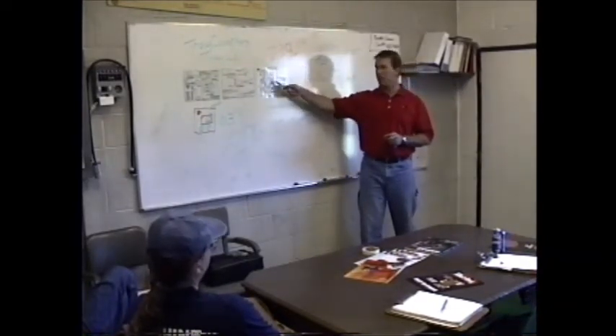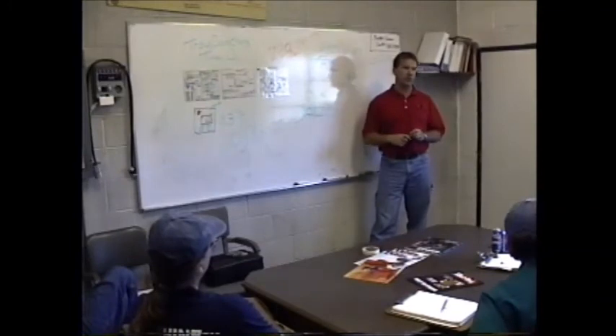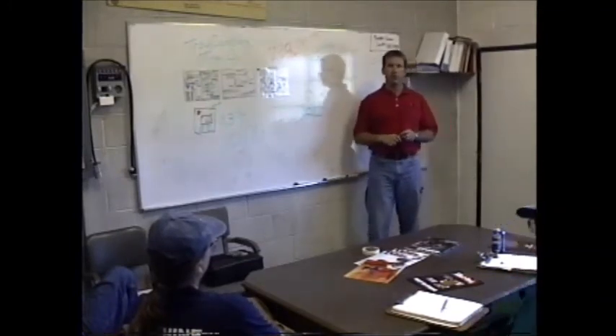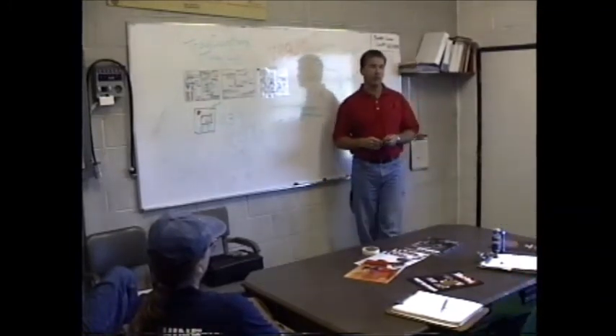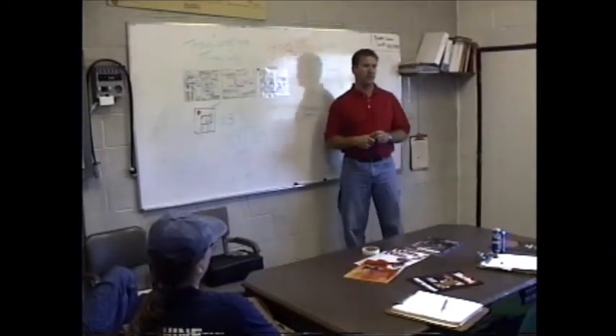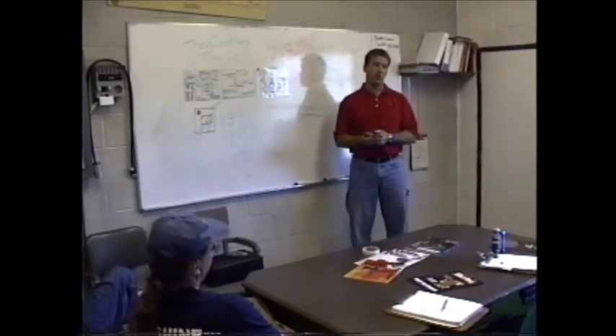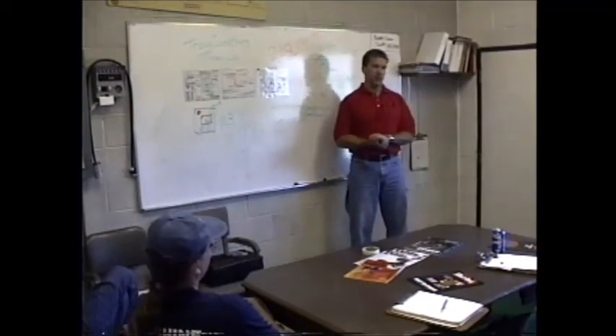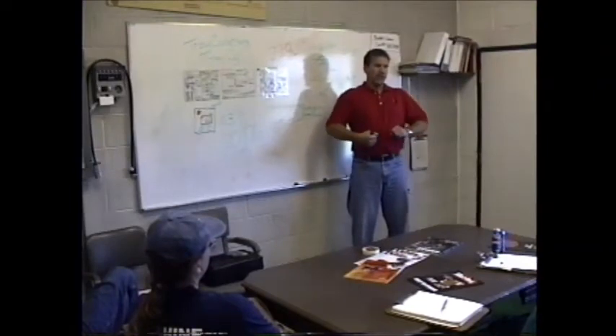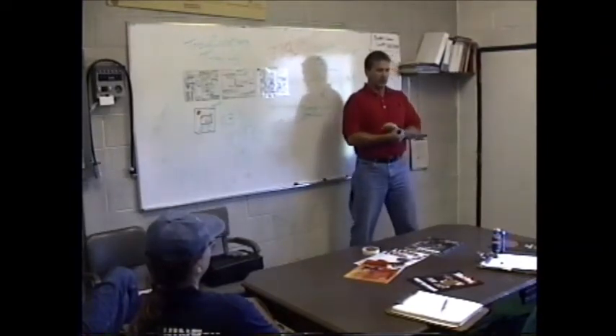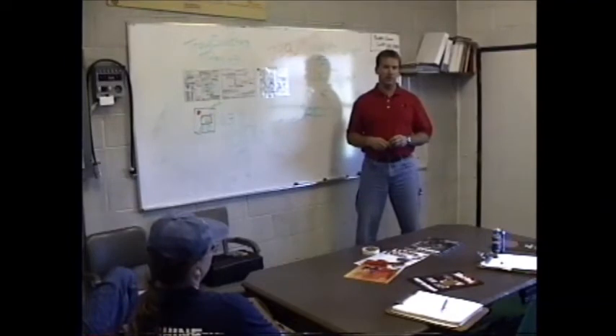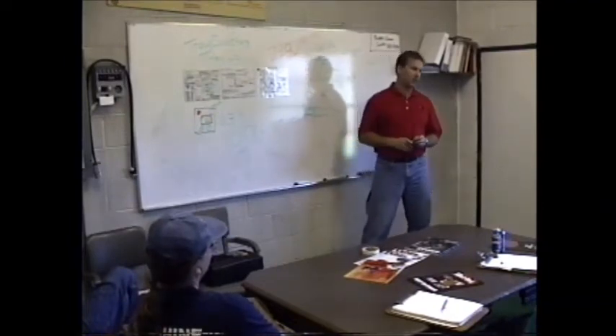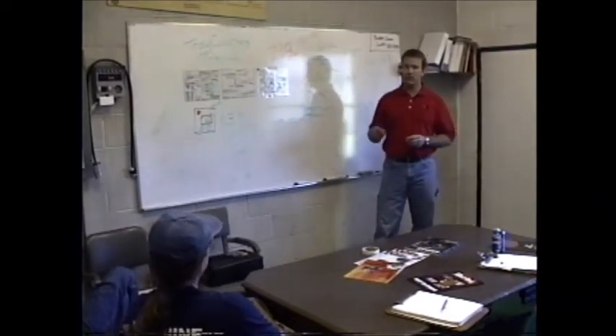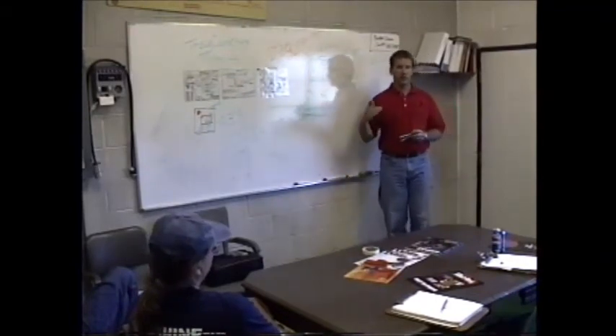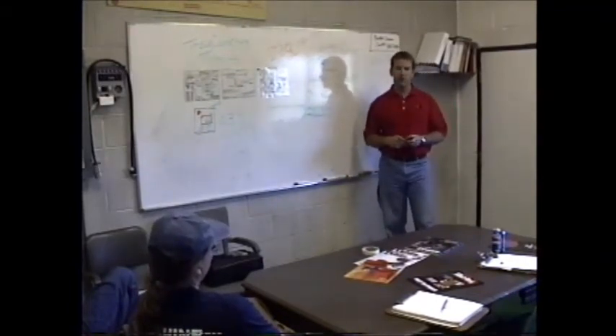and you crank that knob on that air compressor, manual adjust a little bit more. But there's no practical reason whatsoever why you'd ever need to run more than 150 psi of compressed air. You sure as heck don't want to be making CAFS with 150 psi, because you're going to need to have 2-3 really big people on the end of that nozzle that can lean up against a tree while they're shooting that foam, because it's going to be a lot of nozzle reaction.